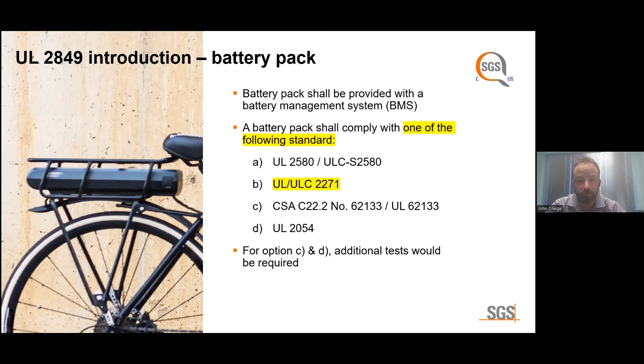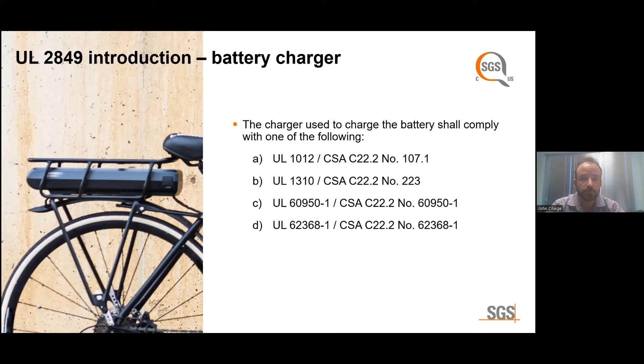On the battery charger, typically we see UL 62368. Sometimes UL 60950, but that standard's being phased out. You could also look under Class 2 or non-Class 2 power supplies, but typically we're looking at UL 62368 for the charger. Now the cables and connectors all have to be approved as well. The cable that's used to connect the charger to the e-bike has to be certified to UL 62. Other connectors can be certified to UL 2251, UL 1977, or UL 2238. Even if the connectors are approved, they need to be rated for the current and voltage of the application. So you have to make sure you have the appropriate type of connector, and that it's also approved.